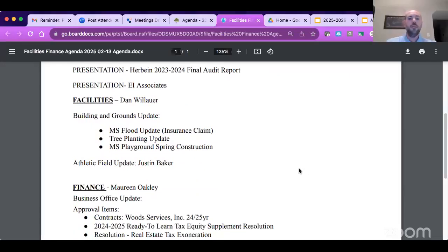Good evening, committee members. I just have a few updates tonight for facilities. One, as you're all aware, we had a gas leak yesterday at Barth. It was reported to me in the morning, just as our crews were done with snow removal. So we went right back to Barth, and I was on the phone with PECO right away. They were very quick to respond. They were on our property within 45 minutes. We found 2 gas regulators outside, which is a blessing. There's no interior damage or any smell inside. They were able to fix both regulators in a timely manner and give us the green light, and we were back in session today.